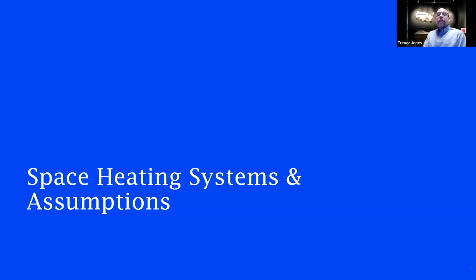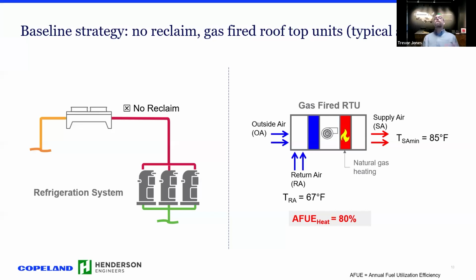So the space heating systems and assumptions. Our baseline strategy was no reclaim and simple gas-fired heating units on the rooftop units, which is typically standard. So we're looking at return air of about 67 degrees, a minimum supply air temperature of 85 degrees for the heating side. And we tried to maintain the minimum heating set point at 85 degrees supply air temperature throughout. So that'll be the same for the water source heat pump. And then as we start getting into the heat reclaim.